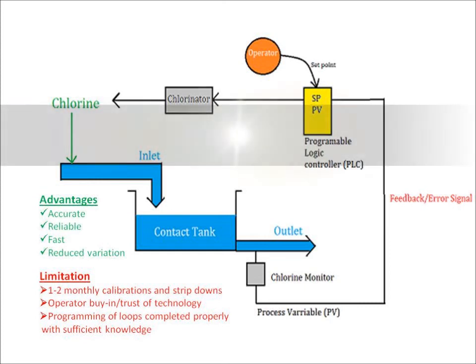The controller compares the process variable and set point to decide the suitable output to send to the chlorinators. This in turn alters or maintains the amount of chlorine added to the inlet of the contact tank. This represents a closed loop system, which provides accurate, reliable control with reduced effects of parameter variation, with no manual intervention required.